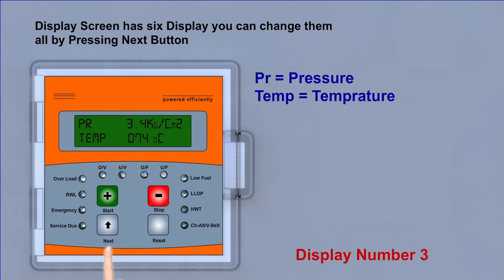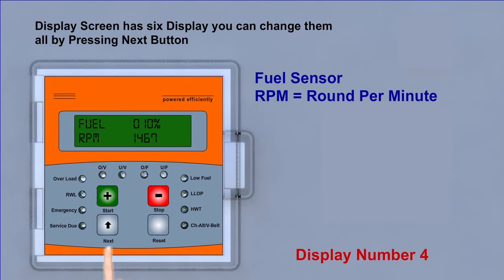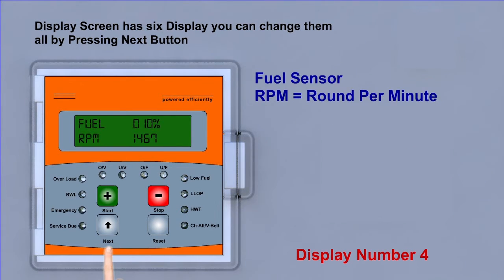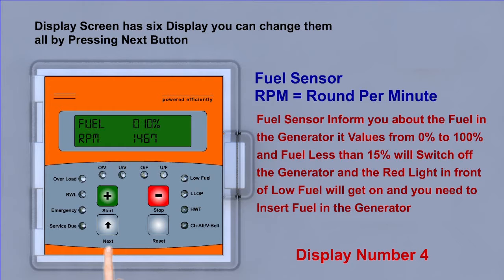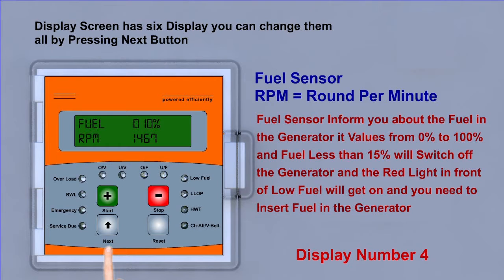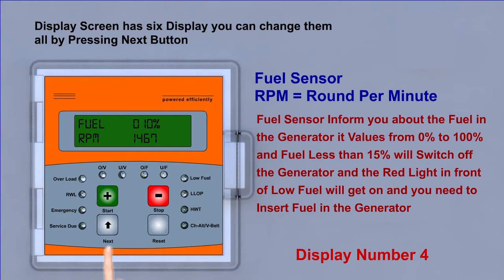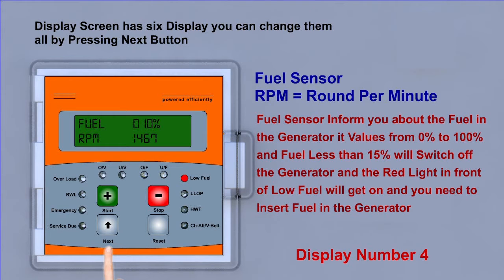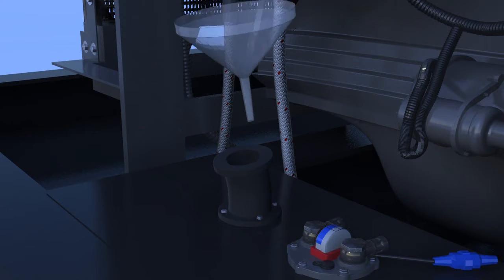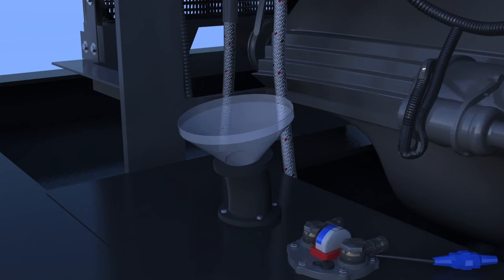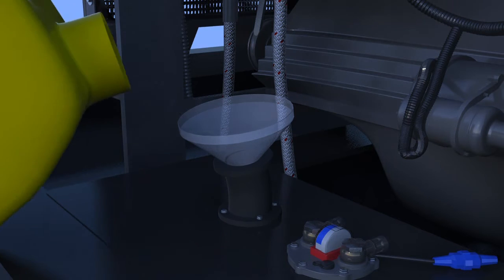Display fourth, fuel sensor, RPM round per minute. Fuel sensor informs you about the fuel in the generator. It values from 0 to 100%. And fuel less than 15% will switch off the generator. And the red light in front of low fuel will get on and you need to insert fuel in the generator.